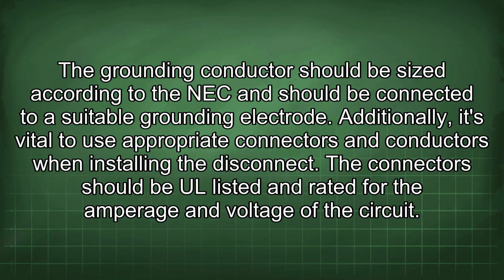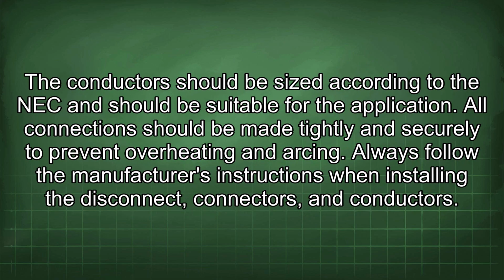Additionally, it's vital to use appropriate connectors and conductors when installing the disconnect. The connectors should be UL listed and rated for the amperage and voltage of the circuit. The conductors should be sized according to the NEC and should be suitable for the application. All connections should be made tightly and securely to prevent overheating and arcing. Always follow the manufacturer's instructions when installing the disconnect connectors and conductors.